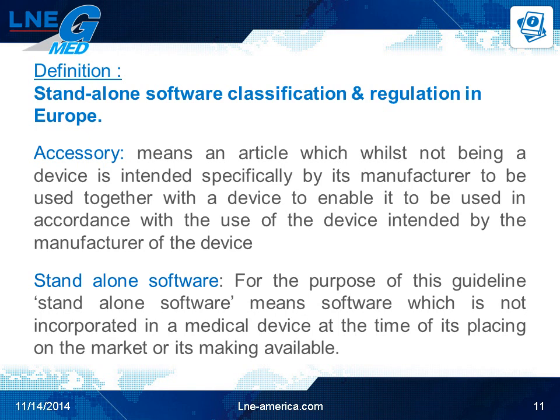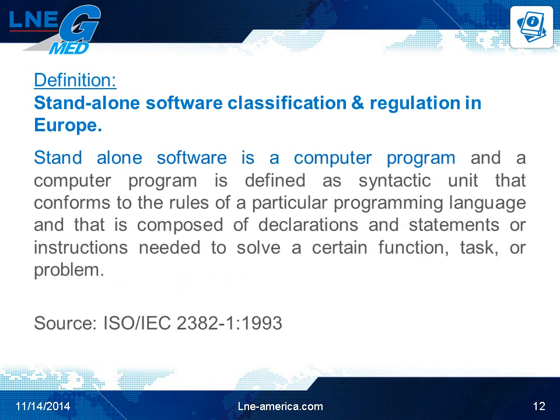An accessory is an article which, while not being a device, is intended specifically by its manufacturer to be used together with a device to enable it to be used in accordance with the use of the device intended by the manufacturer. Standalone software, for the purpose of this guideline, is software that is not incorporated in a medical device at the time of its placing on the market or its making available. Standalone software specifically is a computer program, defined as a syntactic unit that conforms to the rules of a particular programming language and is composed of declarations and statements or instructions needed to solve a certain function, task, or problem — a definition that comes from ISO/IEC 2382-1.